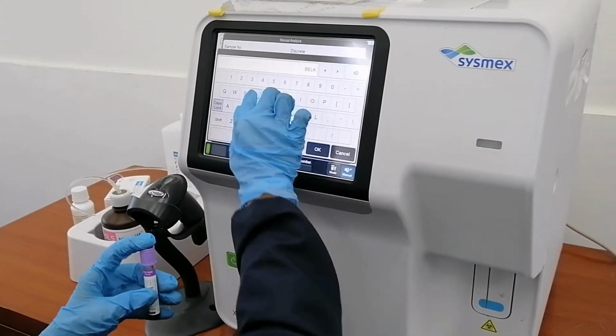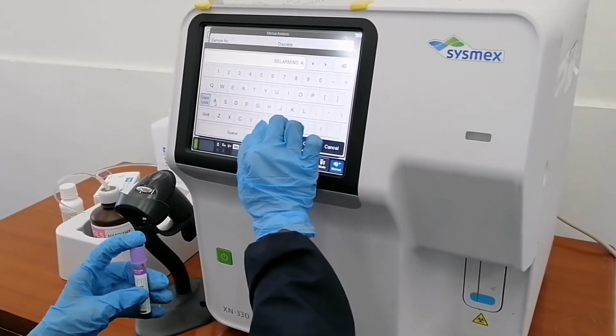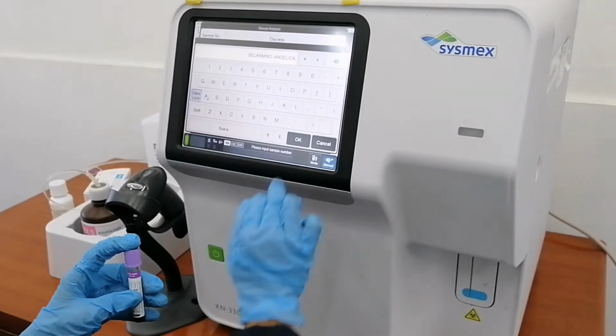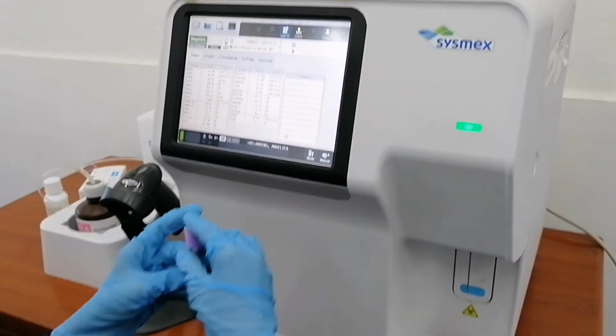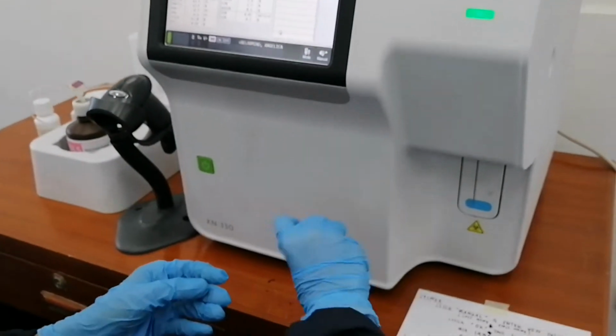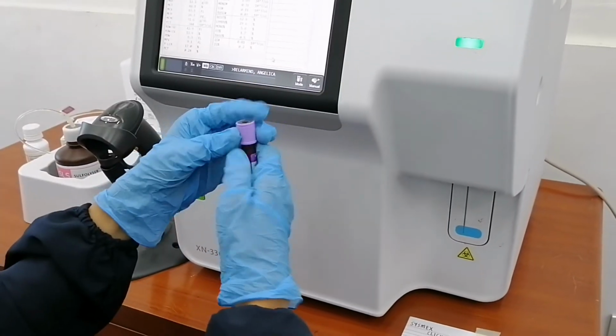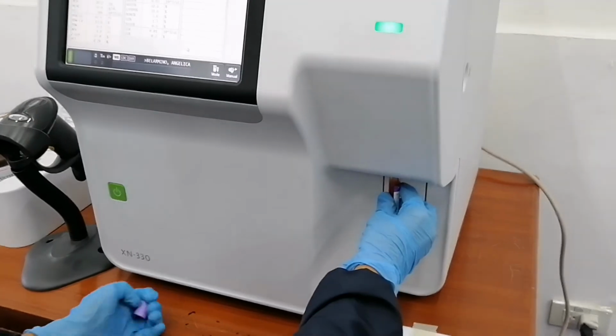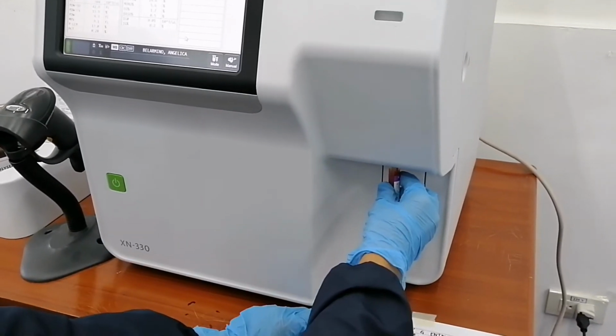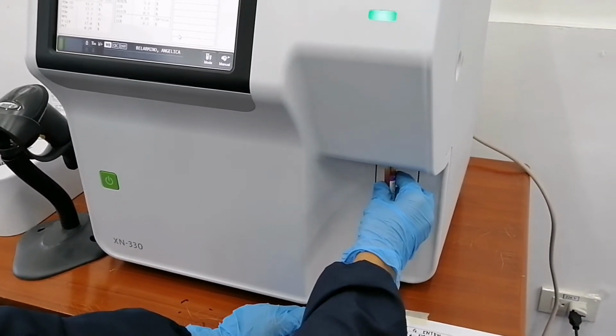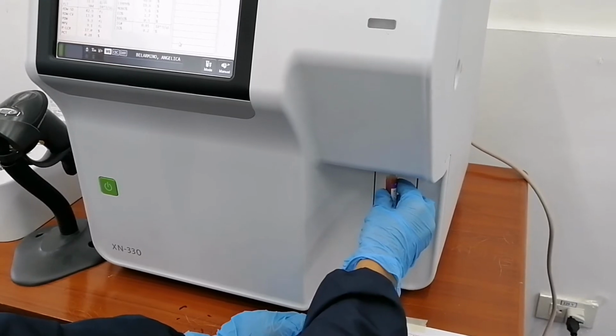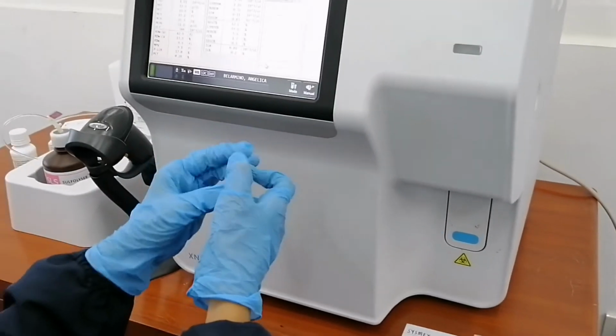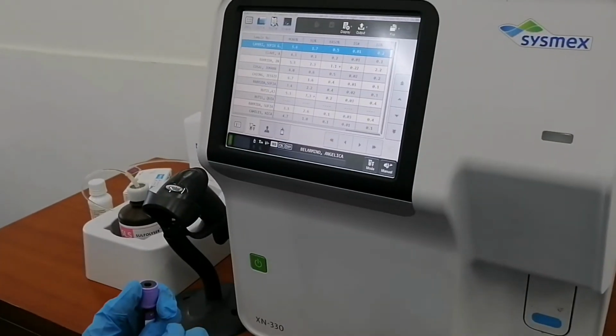Using Sysmex for automated CBC and platelet count. Click Manual and enter New Patient. Click OK 2 times and then mix the sample before aspirating. Place the tube on the probe and click the Aspirate button. Wait until done and then wait for the results and view it under the Explorer.